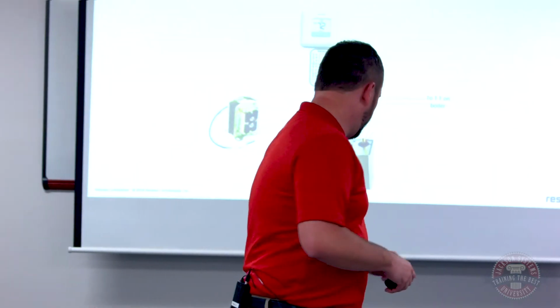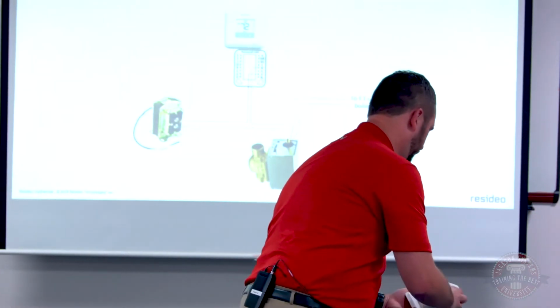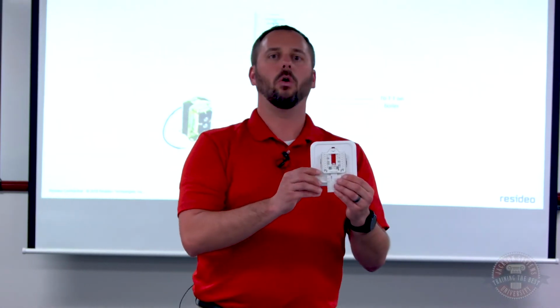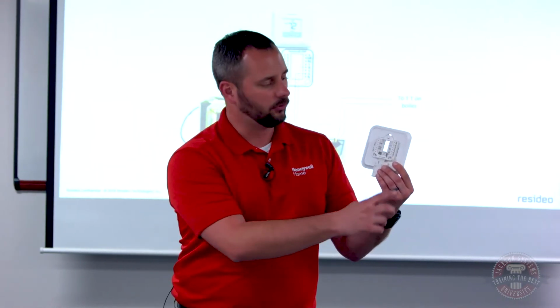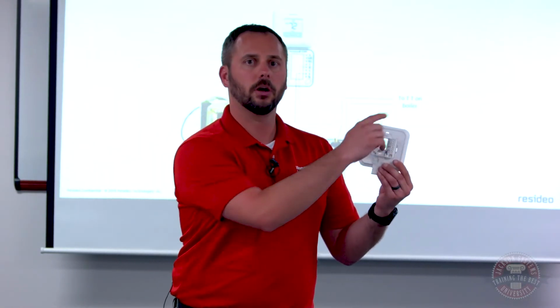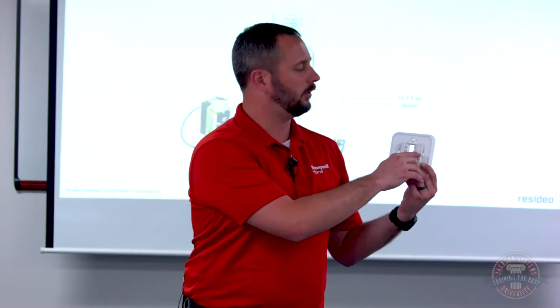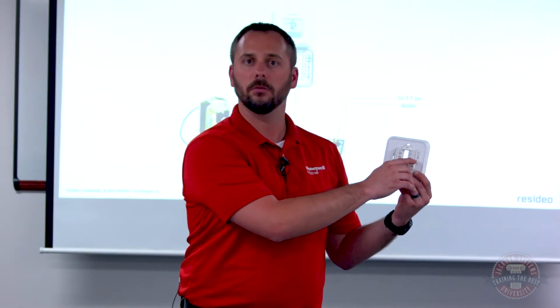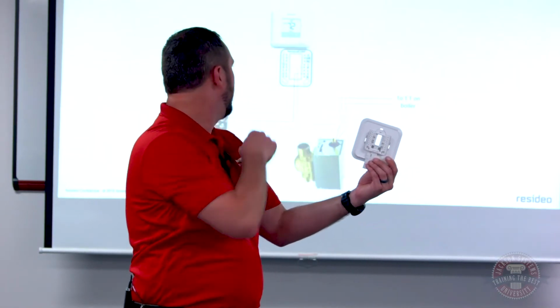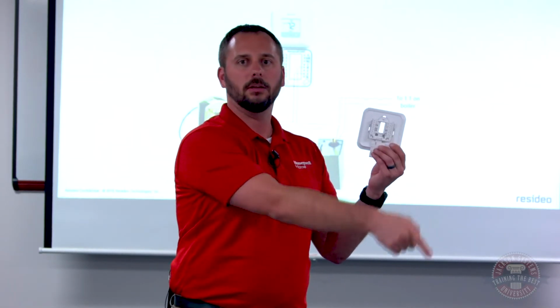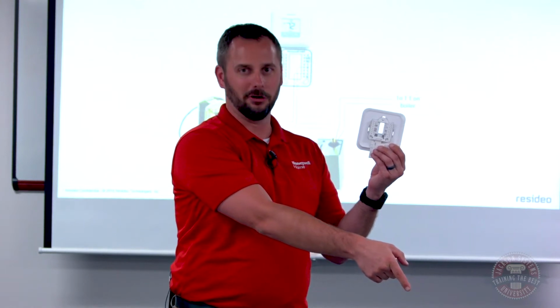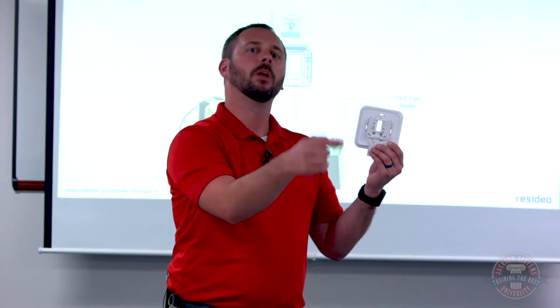So if you look at a thermostat subbase, you'll see a whole bunch of different letters and characteristics. What we're doing is taking 24 volts into R, and then we're going to throw it to different things depending on what the thermostat's doing. So if it's calling for heat, because we're talking about hydronic heating, it's going to basically throw a switch between R and W. Then in this example I've got behind me, we're going to take W down to that zone valve motor, being careful not to hook it to the end switch. The other side of that motor goes back to C on the transformer.